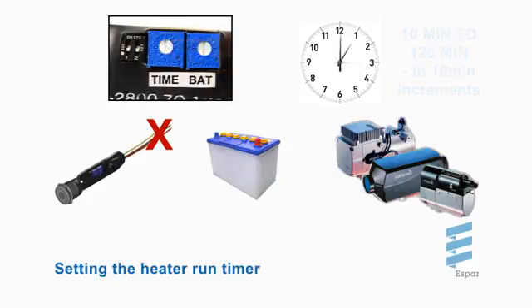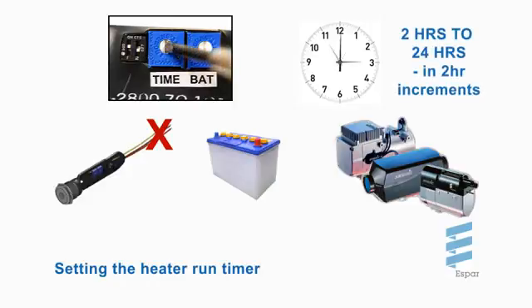The heater run time preset will be read in hours when the dip switch number one is in the up position. The minimum setting is 2 hours and the maximum setting is 24 hours in 2 hour increments.